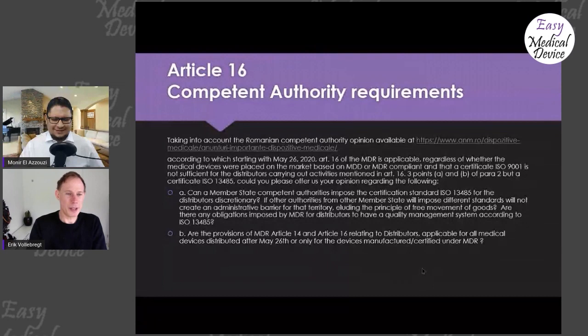Then, if you read the MDR explicitly, it says you need a certificate from a notified body accredited for pacemakers. So not any certification body, and not any notified body, but a notified body accredited for pacemakers. Otherwise, the certificate would not meet the requirements of Article 16.4, I think. And that makes it a small group of notified bodies you can go to. But one thing is important here: we are talking about the distributor, and a distributor is not distributing just one kind of product. So should we appoint many notified bodies in that case? Or appoint a notified body with a really broad scope? Or find a competent authority that is willing to interpret this criterion very loosely.